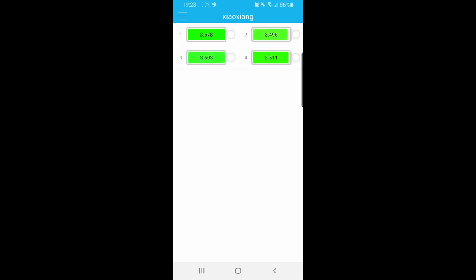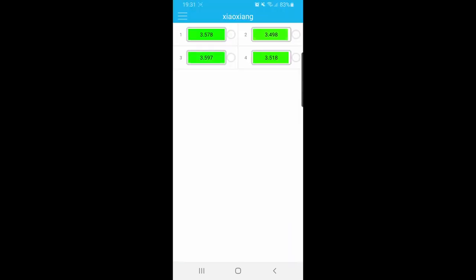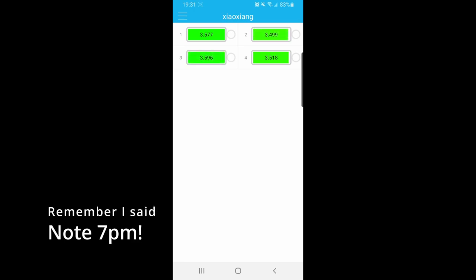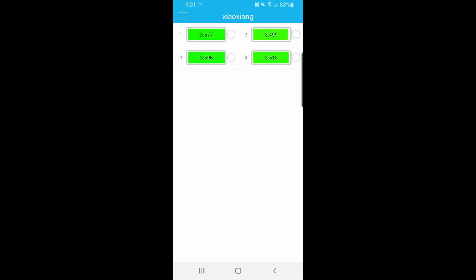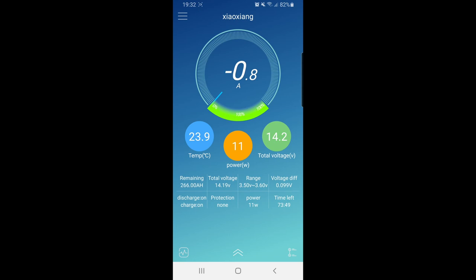Cell three you can see isn't at, I think it was at 3.63V, so that's dropped a little bit. But cell two won't get to 3.5V yet. It just keeps absorbing, and then we can see the charger's in absorption, putting in the odd little bit of current that then goes to zero. And there we go, half an hour after it started balancing. It had got up to 3.5V, even 3.501V. Well it was, it had got up to 3.5V, I promise you it had. And there we are, 3.5V, and there it's below 0.1V.